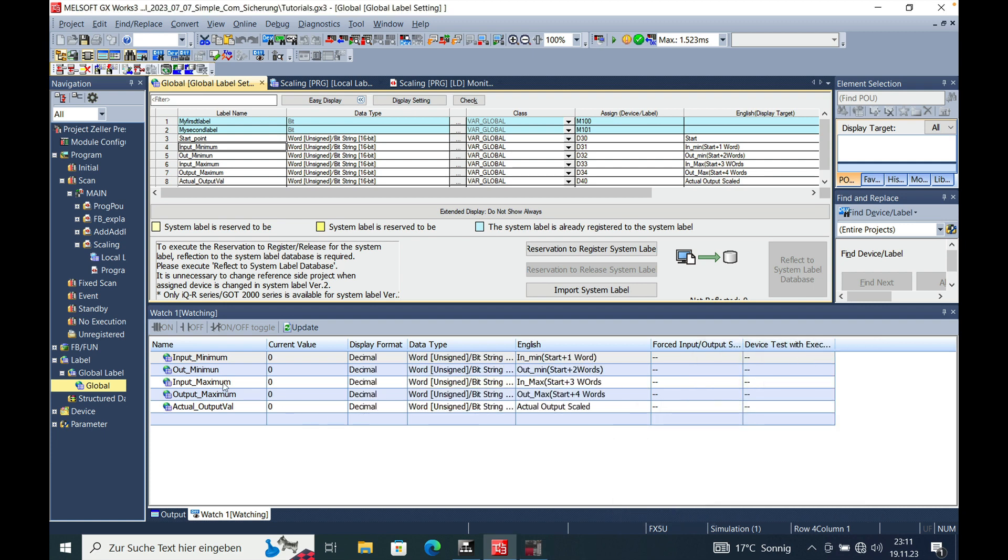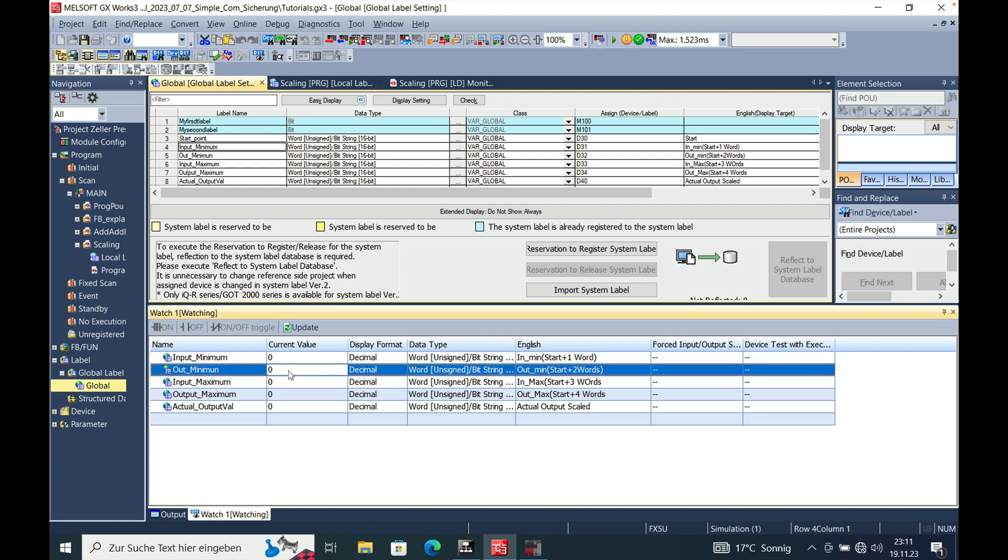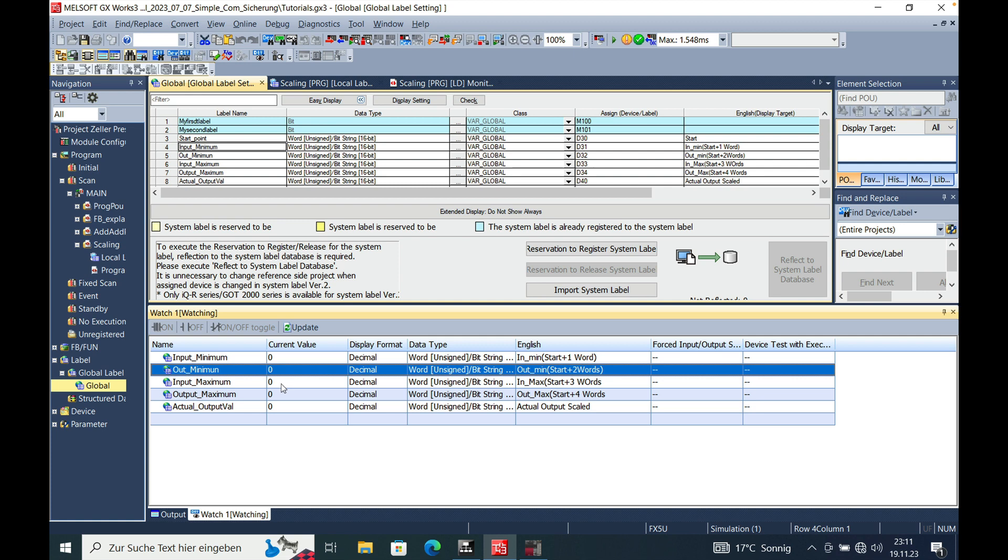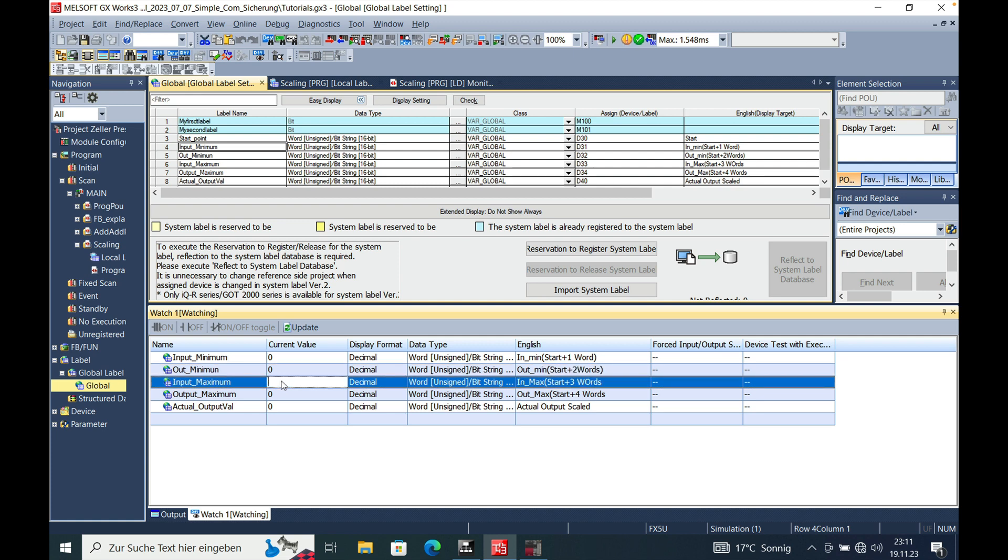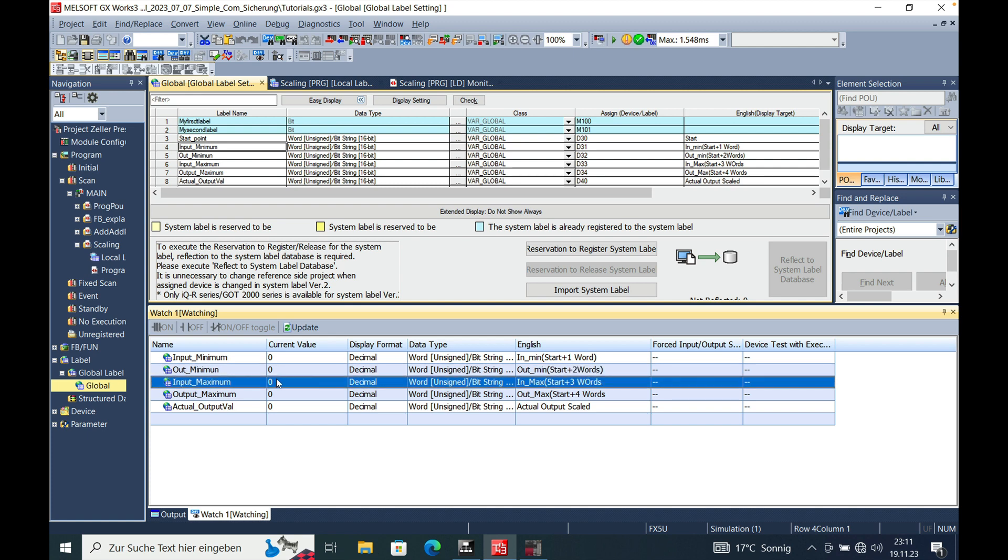So now assuming that we have the FX5AD analog input module, we will have an input minimum which is actually zero. And we will have an input maximum which is 32,000 units. And we have an output. Let's say we have a linear encoder with just 600 mm from zero to 600 mm. So we have an output minimum of zero and we have an output maximum of 600 mm.